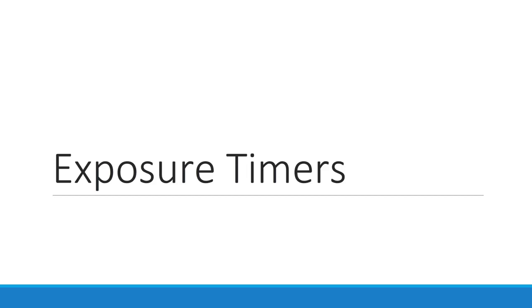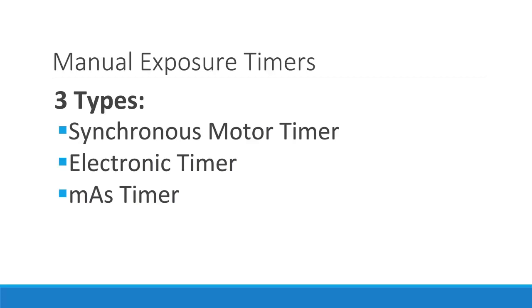In this video we will review the types of exposure timers used in radiography. A timer is part of the high voltage circuit to control the duration of the x-ray exposure. It consists of a mechanical or electronic device that is able to break or terminate the high voltage across the x-ray tube. This takes place on the primary side of the high voltage section when the set amount of time has been achieved. There are three types of timers used on modern x-ray equipment.